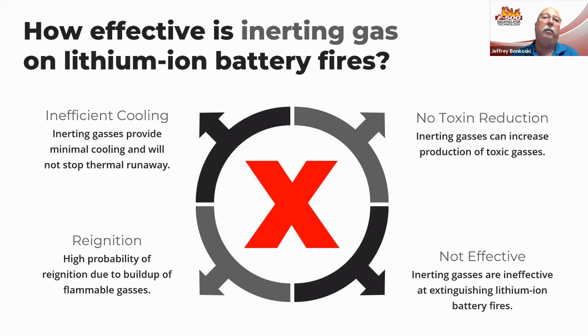But when you're dealing with a flammable liquid, as in the electrolytes of the batteries, and you look at the heat those batteries are generating, those inerting gases can sit there and create an atmosphere where maybe it can't burn, but it's doing nothing to cool or extinguish the batteries, which was the case in Arizona with the firefighters. The inerting gas may have activated correctly and smothered the fire, but it did nothing to eliminate the heat.